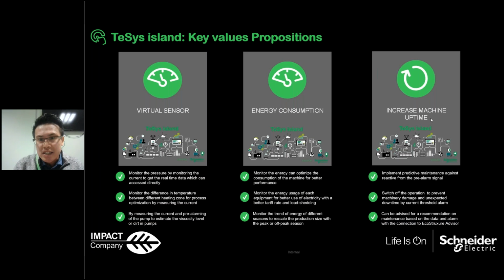So before the unexpected downtime for the motor, before the failure, you can have notifications to operators. Okay, the current is too high now, the temperature is too high now, and then you have to schedule some routine maintenance for the motor. You have to schedule the downtime to inspect the motors, to inspect the system. So you can plan your downtime, and you can plan your spare parts. Basically, if it is sudden unexpected downtime, it costs you too much. You have to buy your spare parts for the replacement. You have to allocate your technician resources to the site immediately. It will cost you too much.